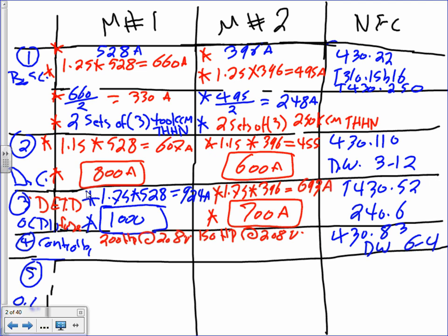What they use is a NEMA that's rated for 240, but the voltage is going to be 208. So you rate them based on the 240. If you go to the 240, guys, what's the size for 200? Number 6, right? And what's the size also for the 150? Number 6. So both of them are number 6. So this will be NEMA number 6, and the same thing, NEMA number 6, both of them. Any question, guys, about that directly? Overload. Both of them are NEMA number 6.